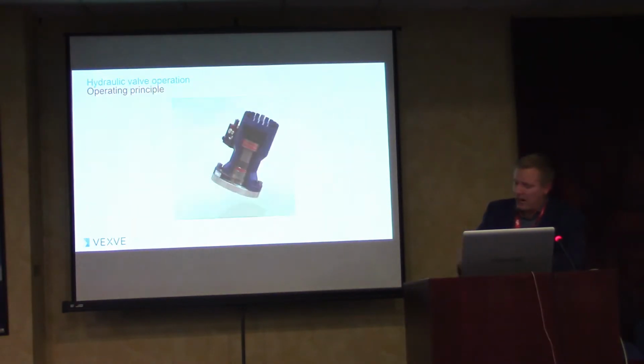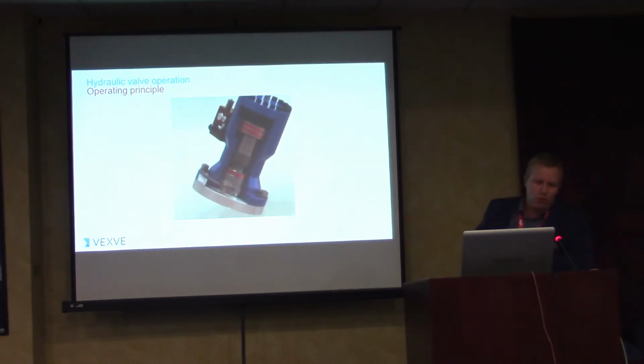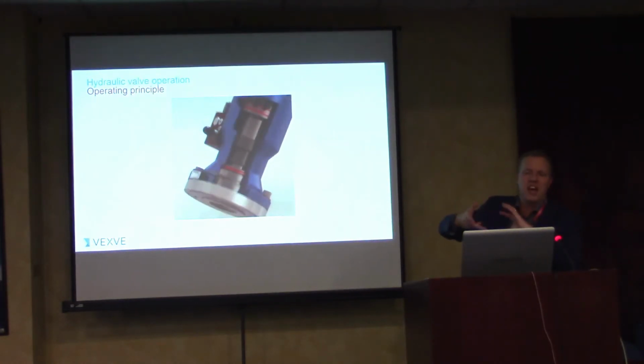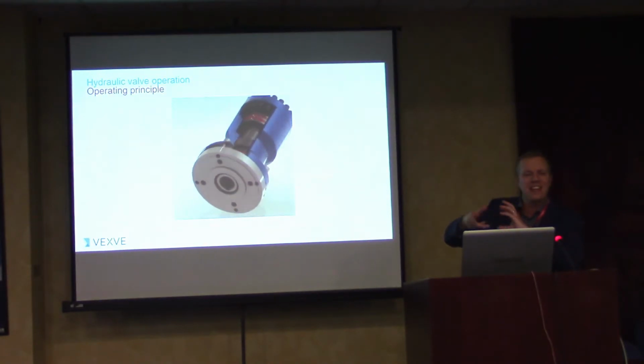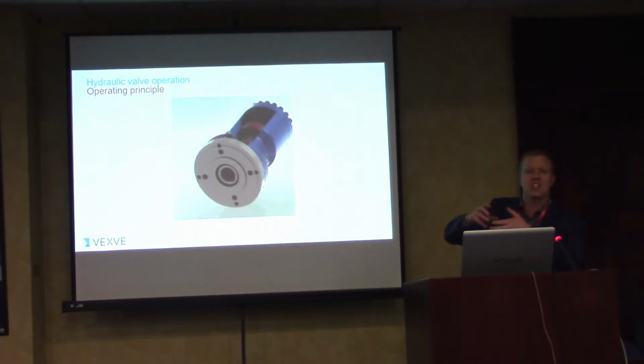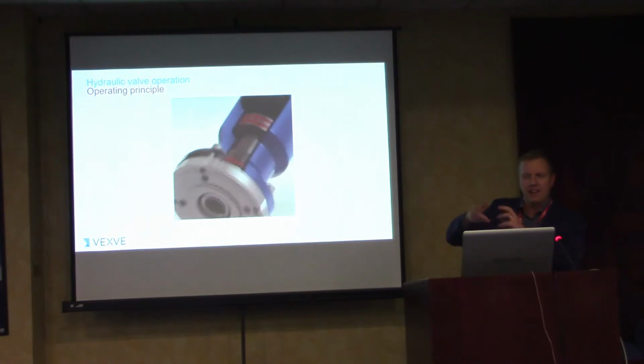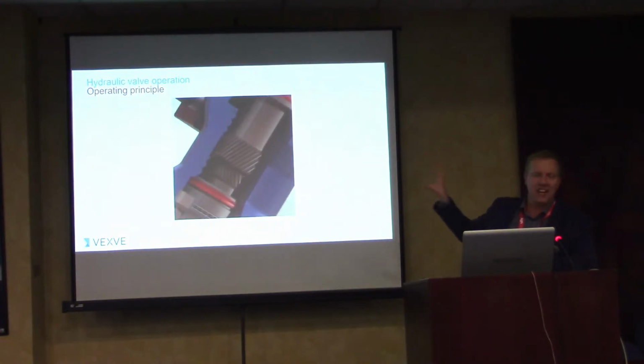Let's see if I can start this video showing the hydraulic actuator operating principle. It's very simple. We have 2 moving parts inside the actuator, which is completely maintenance free, just like these valves. The user never has to go inside this actuator. The only maintenance ever required will be changing the hydraulic oil at intervals between 5 and 10 years.